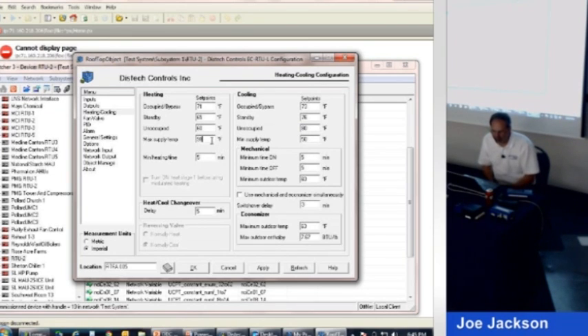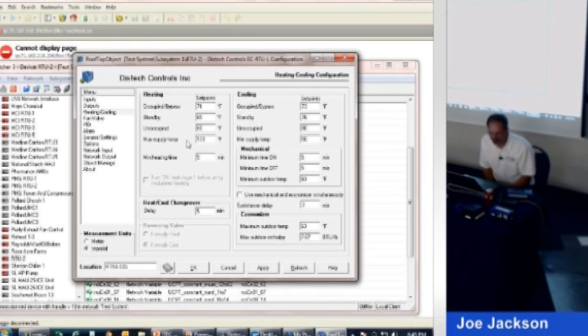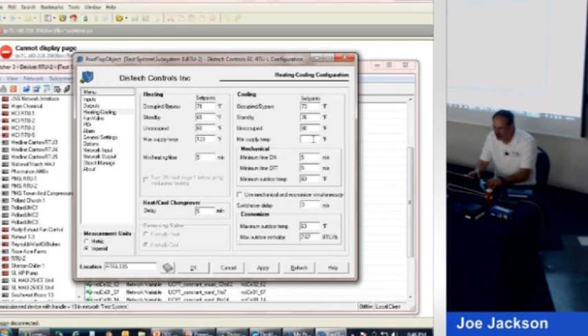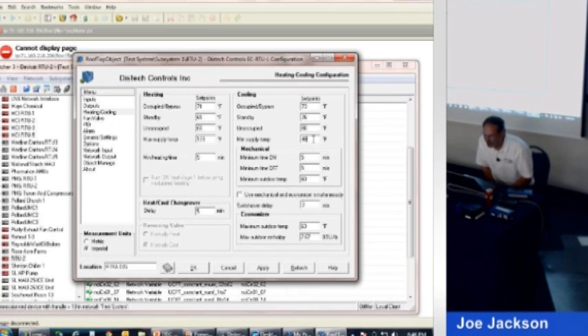And then we got a couple of things we can set up here that can be helpful. We've got a maximum supply air temperature. I'm going to say this is a gas rooftop, so I'm going to let it climb clear to 120. If it was an electric rooftop, maybe you'd want to stop it from going that high. It's just a safety thing. And a minimum, we're not going to let the discharge go below 50. Typically, that would be plenty cold enough, but we know the teachers in the school like to drop the temperature down to 69 degrees, and the filters get a little dirty, and the discharge, we'll say it can go to 48 degrees before it cycles the compressor off. You think, well, that's not all that great, but that's something a normal thermostat can't do. It can't cycle the compressors off if it starts to ice up.